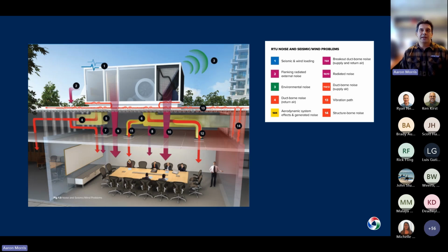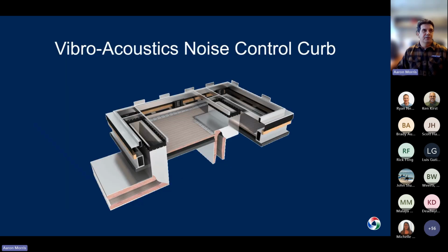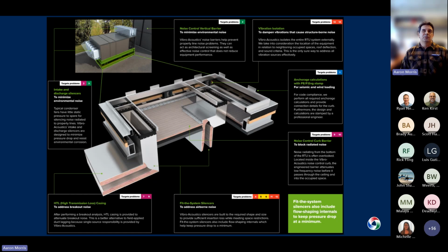Another good way to deal with it would be a concrete equipment pad. If you can do that, then the mass of the concrete will do a good job dealing with that radiated noise and absorbing some of that vibration. If those are not options for you, then we can work with Vibroacoustics to design a noise control curb that will really deal with all 4 sound transmission paths in one piece of equipment. You can see we've got the built-in sound attenuators, which deal with the ductborne noise and the breakout noise. We've got a noise control barrier, which is rated sound media, so we can design it to meet the requirements for the project. And then finally, we have a spring isolated curb rail to deal with that vibration transmission going into the building.